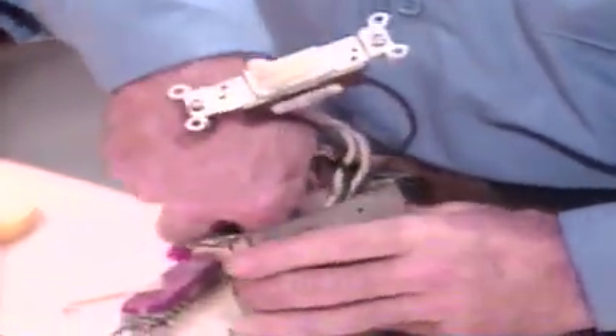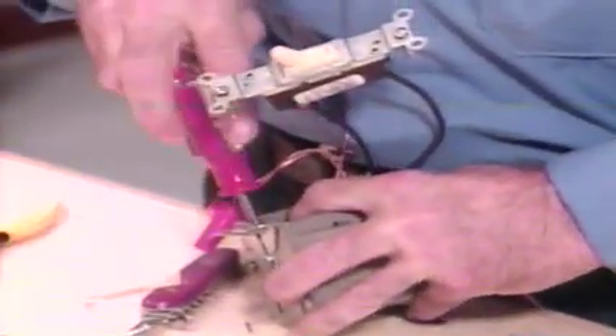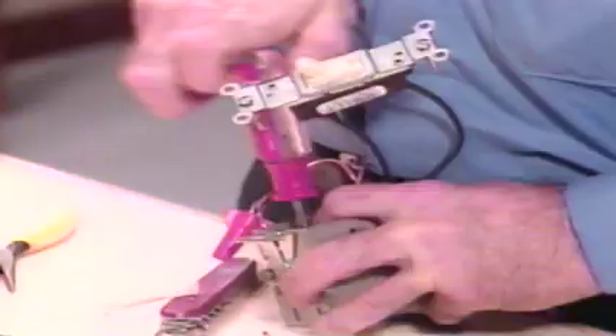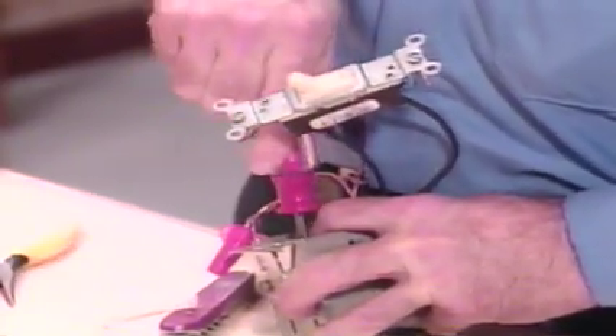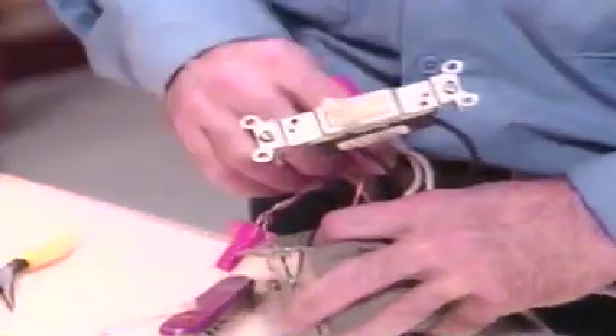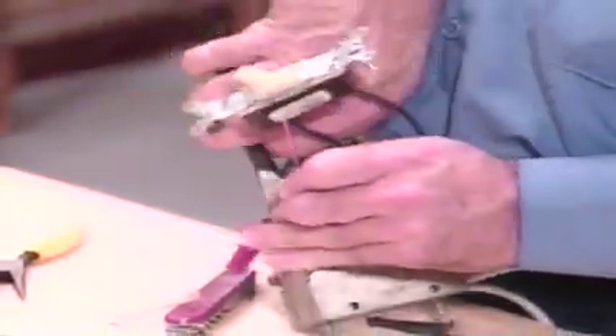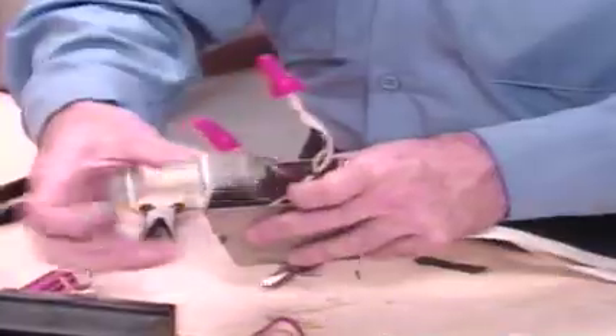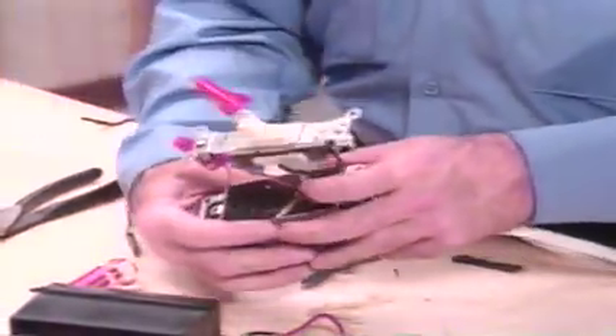No kidding. Now, at the end of the pigtail, you make a loop, just like you did with the black wires, and you put it around the grounding screw in the bottom of the box. Then you screw the grounding screw down. And you put it around which way? Clockwise. Always. Make sure they don't come off. You put it on clockwise, it tends to get tighter the tighter you tighten it. I use a little extra wire there and just clip off what I don't need in the box. Good. There you are. How's that? Nothing to it. Nothing to it at all.